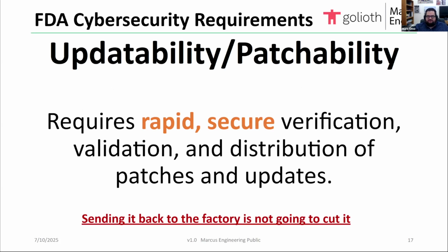You need this to be a feature in your product to allow you to meet this requirement for rapid, secure verification, validation, and distribution. We've often seen products that can't, for example, do secure updates because they can't run the cryptography required to meet the current best standards. We've seen products that don't have interfaces or software support, where adding this would be more complicated than the entire product, blowing up their development timeline and budget.